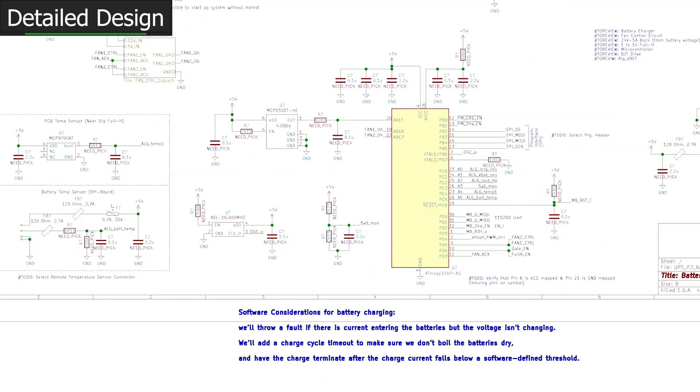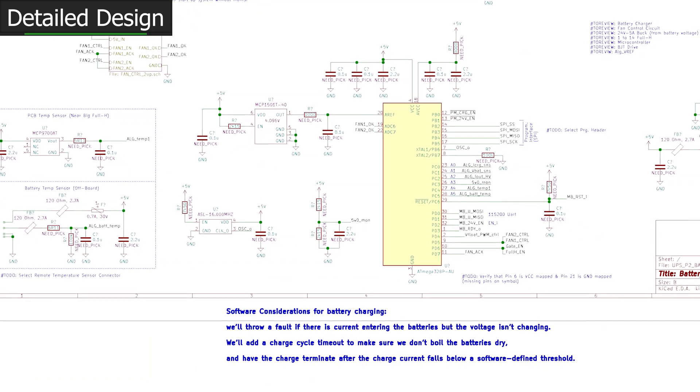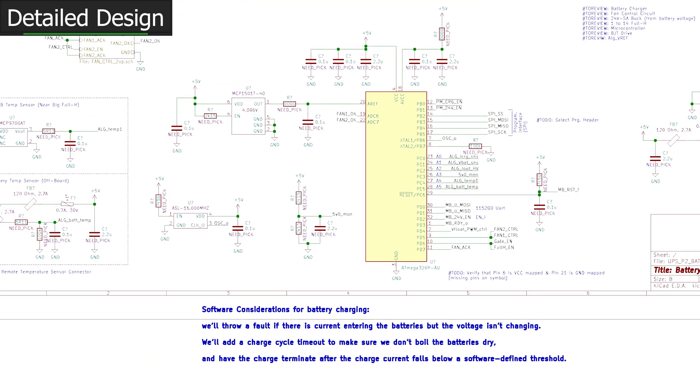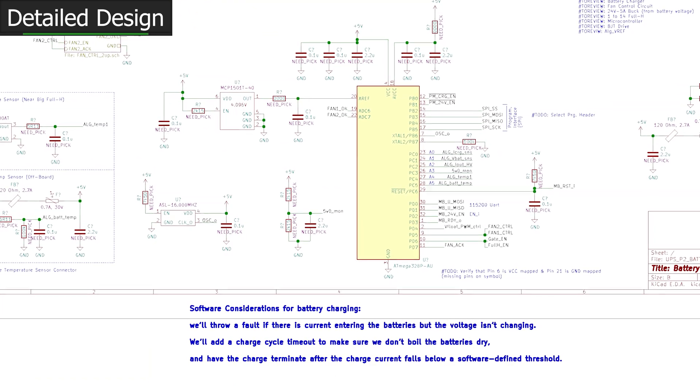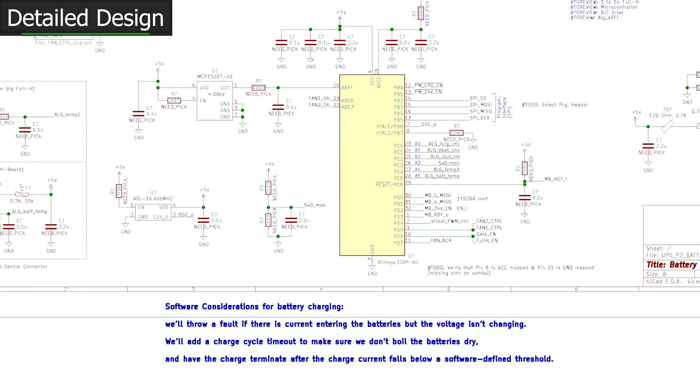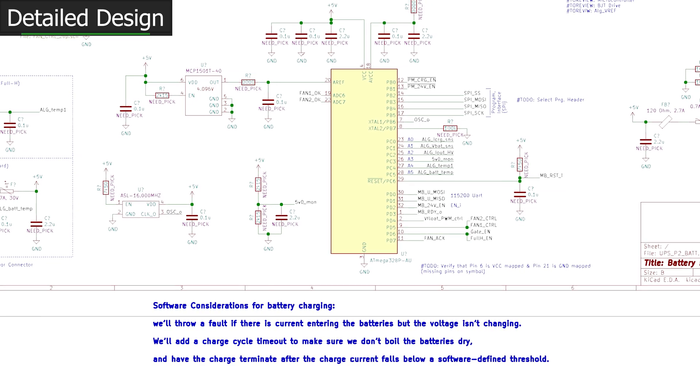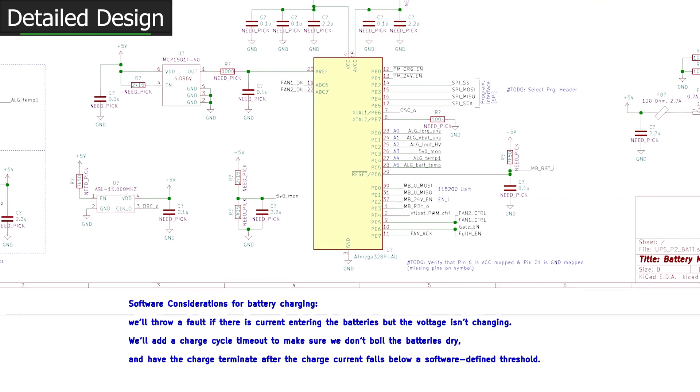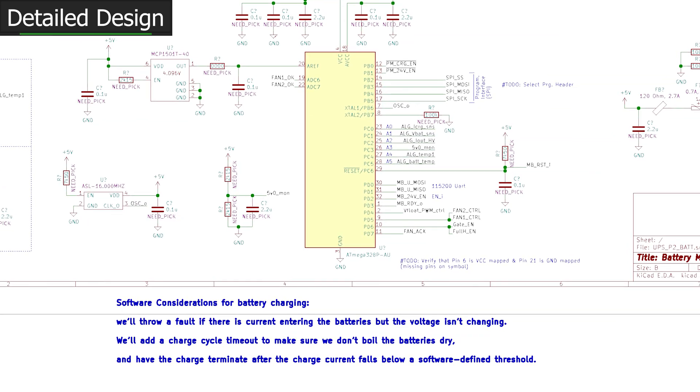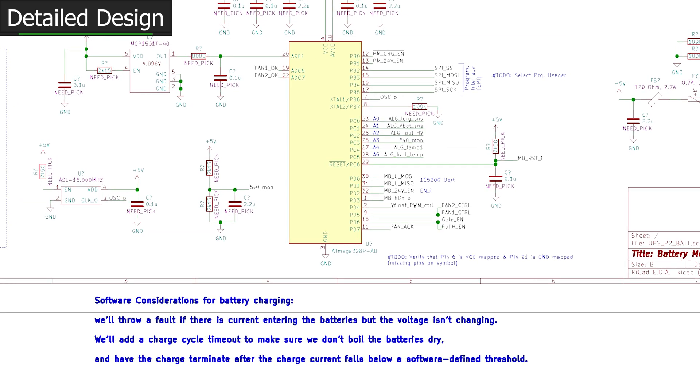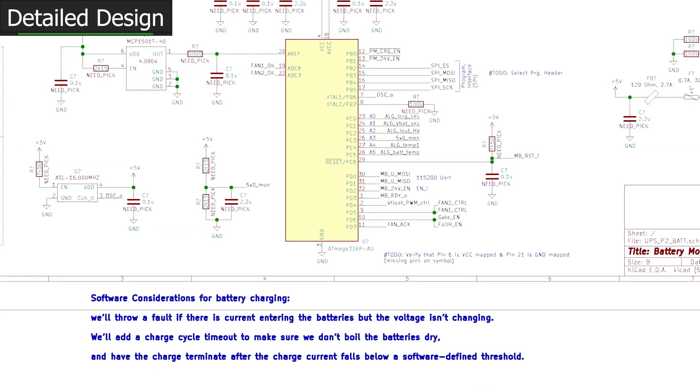To make a long story short, all we need to do to charge our batteries is enable this power supply. I want to make sure that we can keep an eye on voltage and the charge current as well. We need to remember that our software took on some responsibility. It needs to use that information, it needs to use the voltage and current to throw a few critical errors. First, we need to throw a fault if there is current entering the batteries but the voltage isn't changing. If the batteries are charging too slowly or too quickly, if the effective battery capacity is too low to really work, we need to add a charge cycle timeout as well to make sure that we don't boil the batteries dry and have the charge terminated after the charge current falls below a software-defined threshold. I know that we CAN float charge forever, but if we have a little more precise control, that will enable the use of AGM batteries as well.